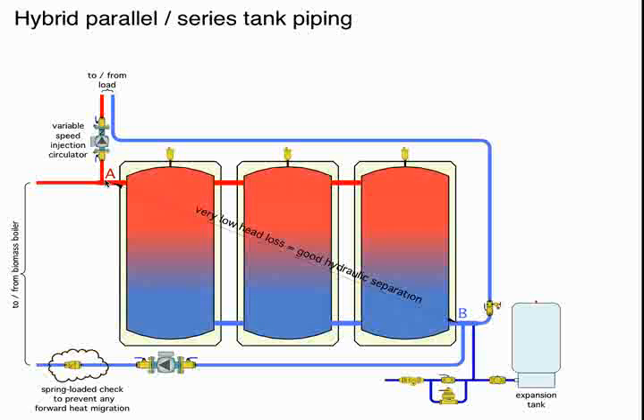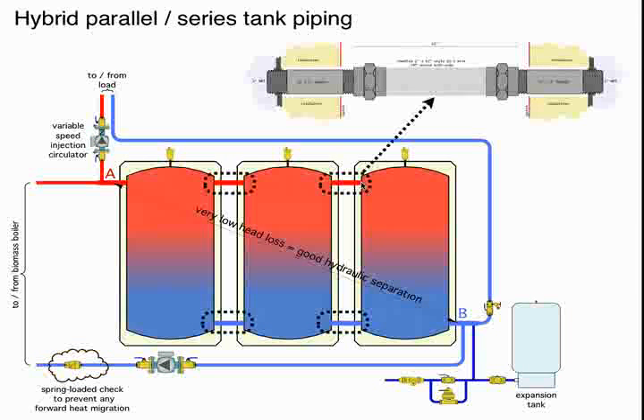We have a heat source putting hot water flow in here. Here's our load taking off. Our load return comes back down here. So the points A and B here are set up essentially in a reverse return arrangement to try to balance the flow. In theory, the stratification in all three tanks should be identical. There might be very small variations in that, but I don't feel those variations will be significant. And it really requires you to have short connections here. The shorter these connections are between the tanks, the closer this approximates a single large tank.